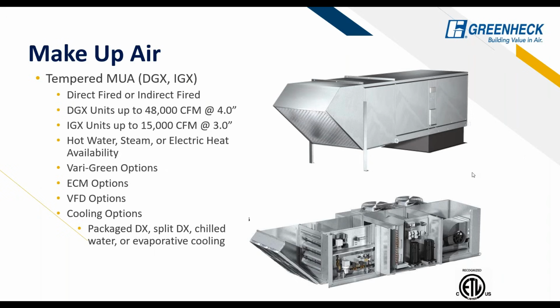Going into makeup air, we have some options with tempered MAUs with direct fired and indirect fired gas. Now, direct fired gas is 100% acceptable in kitchen applications. The only time we can't do it is in sleeping quarters. So there's no issues with doing direct fired gas with kitchens. I do know there is some hesitancy around direct fired gas, so there's no problem going indirect fired gas, whichever you might prefer.